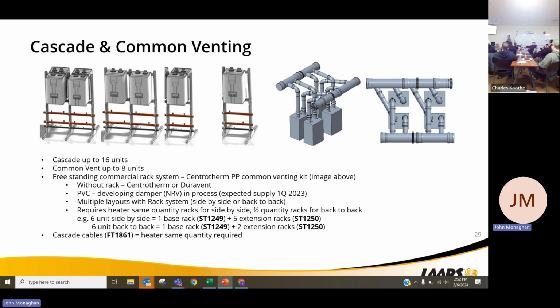If we're going to be doing common venting, we are able to common vent it, and we do have racks and pieces for it. You can common vent up to 8 units, and you can cascade up to 16 units. Again, we can take care of most of your hot water demands with this system. It'll be Centrotherm or Duravent. We do have racks available for it. We have plumbing kits available for it, where it'll do all of your plumbing underneath of it as well.